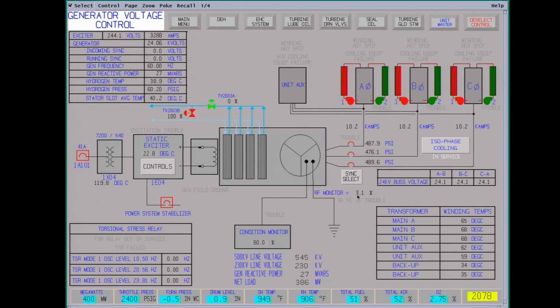They can pick up weird frequencies, anything outside a 60 cycle. If you have arcing, it's going to show up as a frequency on the line. So this is looking for arcing of the generator windings. Condition monitor. This is looking for particulate and hydrogen. It takes a slipstream of hydrogen. So it's looking for particulate from insulation that's breaking down or burning.